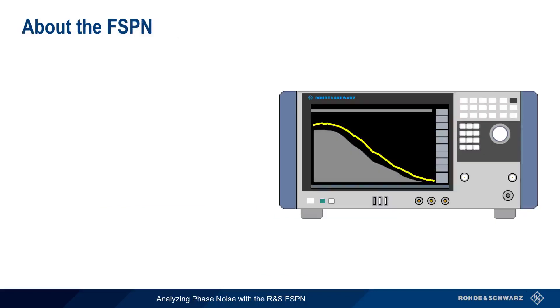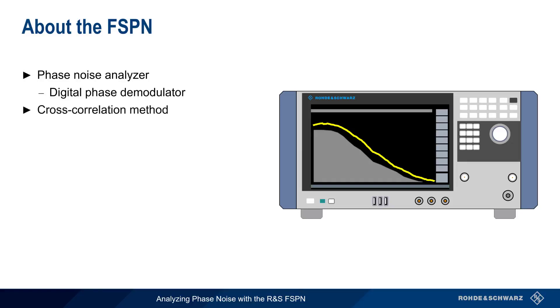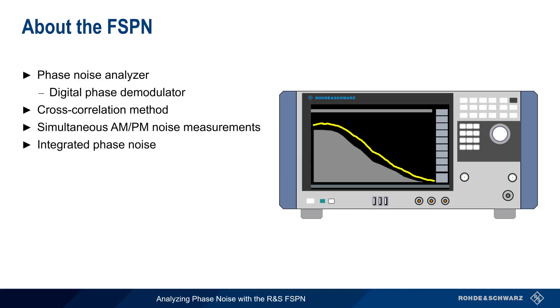Let's start with a brief overview of the FSPN. The Rohde & Schwarz FSPN is a phase noise analyzer that measures phase noise directly using a digital phase demodulator. The FSPN is configured with a second measurement path that allows phase noise measurements using the cross-correlation method, which improves both speed and sensitivity. In addition, the FSPN can make simultaneous but separate measurements of amplitude and phase noise, can make integrated phase noise measurements, can calculate Allan variance, and can be used to characterize voltage-controlled oscillators by means of integrated DC sources. In this presentation we'll focus on standard phase noise measurements, but separate presentations are also available on many of these other topics.